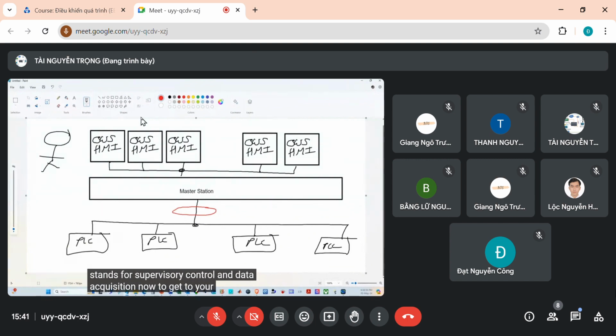Now, to get to your question, Timbu: the operator sitting here can have a level control sitting on that PLC. If the operator puts that control into manual, they have to change the output from 0 to 100% themselves - that's manual control. If the operator puts that controller into automatic, the PLC controls the output itself. So your question was, is SCADA an automatic or a manual control? SCADA is what you want it to be, but it consists of automatic data collection - supervisory control and data acquisition means we collect information and send it out automatically, but the control itself is up to you.